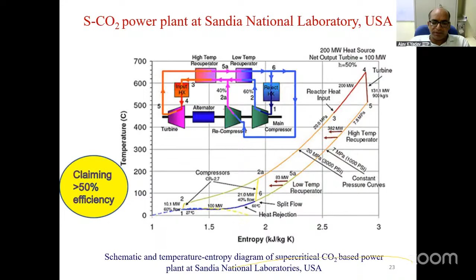So what are the challenges in developing the supercritical CO2 plant? In a normal gas turbine, the pressure ratio is around 8 to 10. Here the pressure ratio is less, around 2, but the pressure range is 90 to 140 bar. In an air gas turbine, suction pressure is 1 atmosphere and discharge is 8 bar, very low pressure. Here it's 90 bar and 140 bar. The compressor and turbine parts must be capable of holding that much pressure. This is an important challenge.